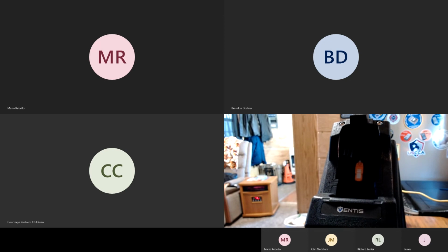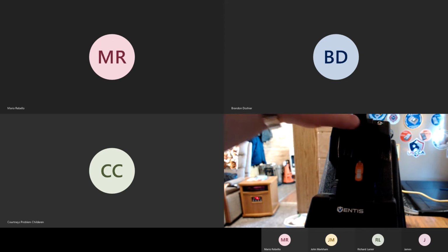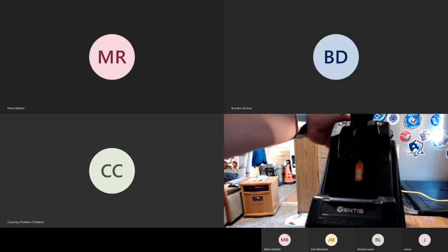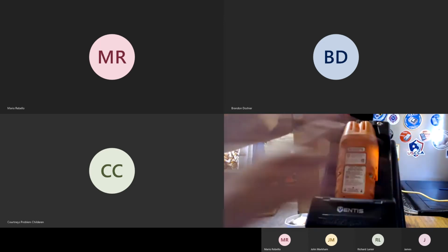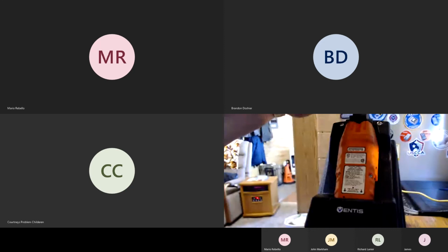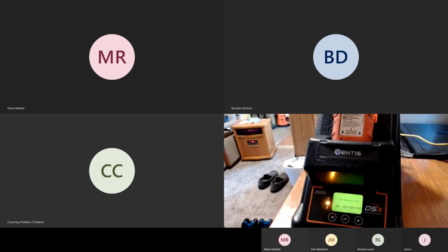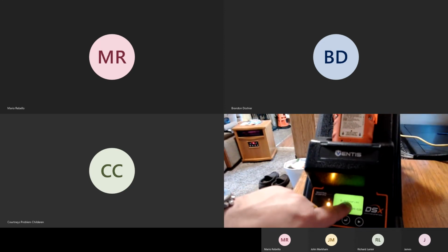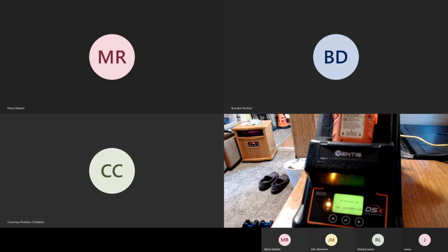All right. So, to dock the instrument, as we talked about earlier, what you're going to do is just lift up on this little cone right here, take the instrument, set it in face down, and close that little cone. Down at the bottom, you'll see that my yellow light came on, and it says Discovering on the docking station screen. The reason for that is it's now reading the instrument, and at that point, it's going to go through and see what it needs: if it needs a calibration, if it needs a bump test, diagnostics done, record keeping, anything like that.